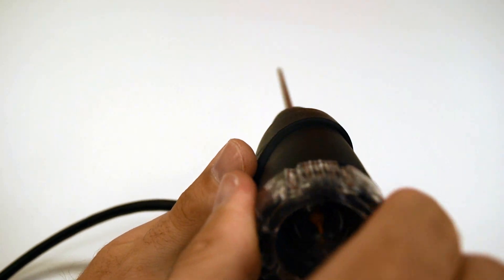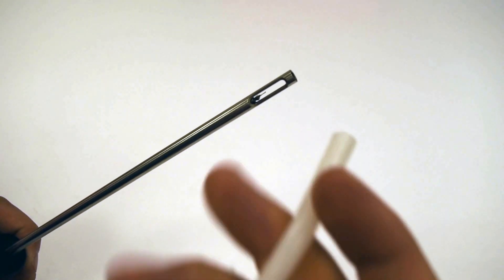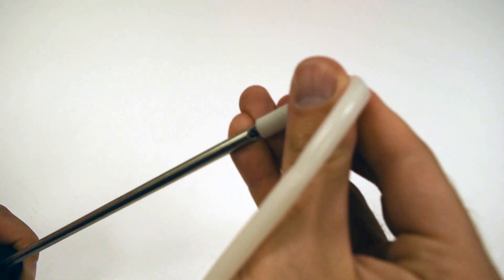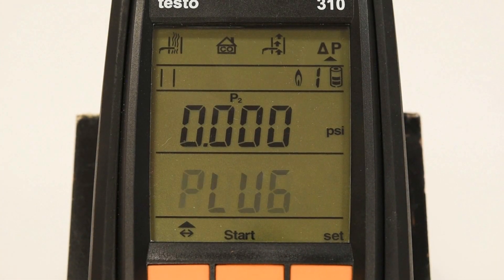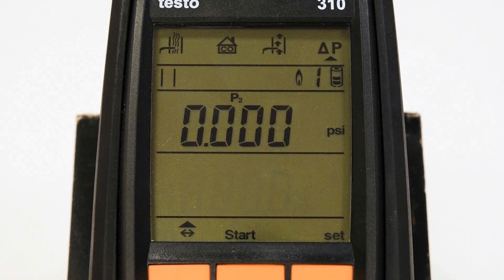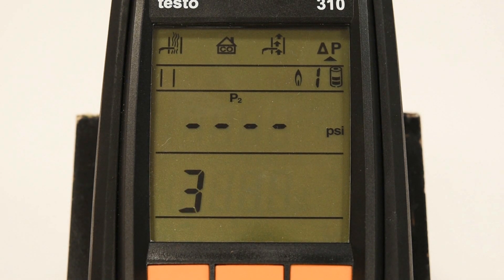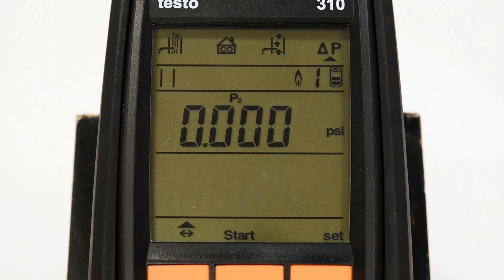Once the plug is secured in the probe handle, secure one end of the silicone hose supplied in your kit to the end of the probe shaft, making sure the hose covers all of the openings in your probe. Start your measurement with the start-stop selection indicated above the center orange button. The display will begin a countdown to zero the pressure reading. Once zeroing is completed, connect the other end of the silicone hose to your measuring point. After the measurement is complete, press the center orange button again to stop your measurement.